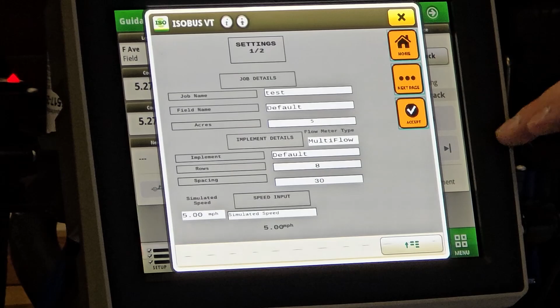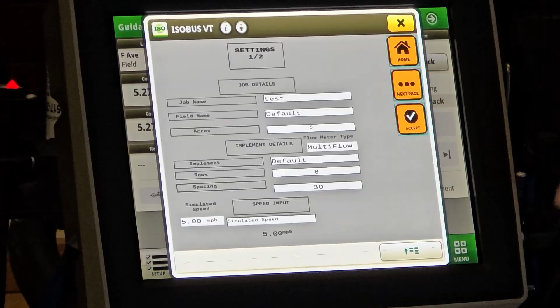So you can see how that flow rate adjusts. Going back to the settings here, same thing. This one has a little bit of a newer software version on it. This is that newer version I said was coming out for 25. There's a different type of magnetic flow meter that can be used as well.